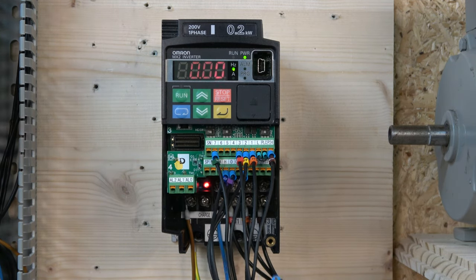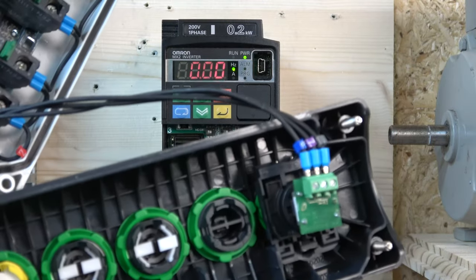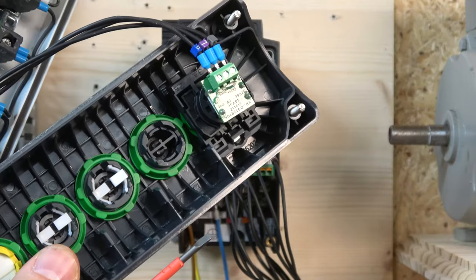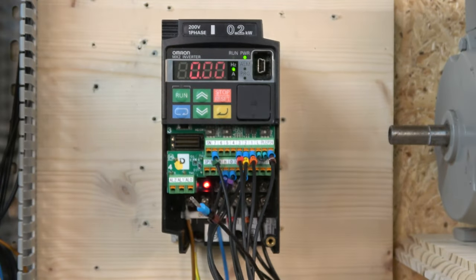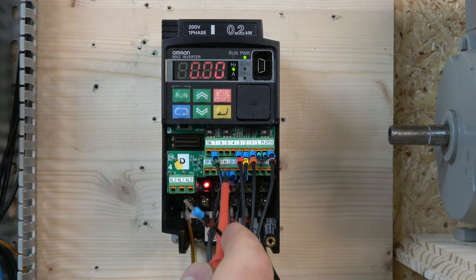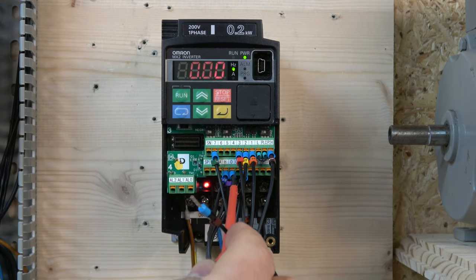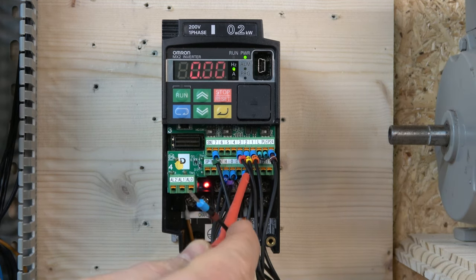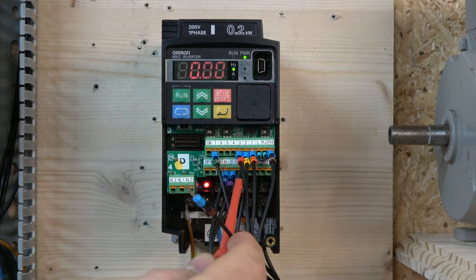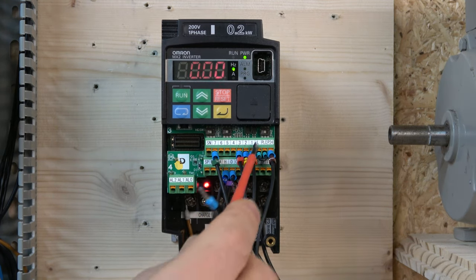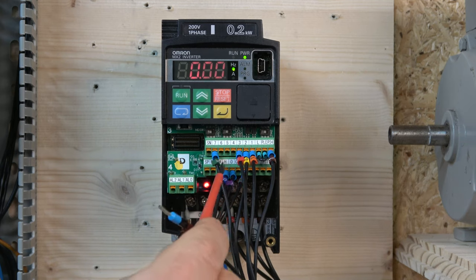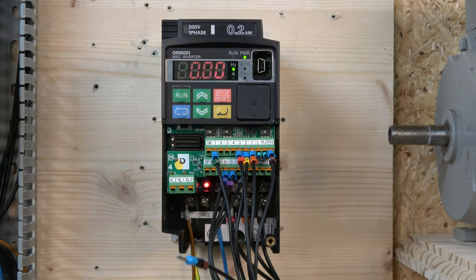That's how we have set the station up. When a normally closed emergency switch is working, as soon as the power will disappear from terminal 3 it will trip out. And when it comes down to a potentiometer, we've got the potentiometer in there. Here we go, three terminals are coming out and we are using voltage for it. So it will go into H, then it's going to go into O, and then it's going to go into L right here on the bottom.